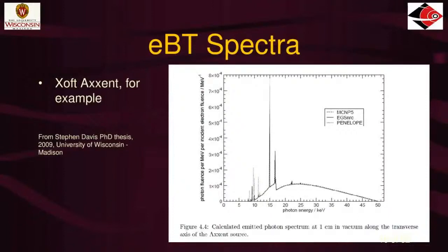Here is the calculated energy spectrum of an electronic brachytherapy source — the Xoft Axxent — shown from three different Monte Carlo codes on the same graph. This is in vacuum, so there's no attenuation in air, water, or tissue. It looks different from a standard X-ray beam spectrum and is lower energy. The filtration is different — it comes out through a water cooling catheter, whereas standard beams are filtered with aluminum, copper, or materials like a Thoraeus filter. X-ray beams are filtered for different purposes: to treat patients, harden the beam, or for diagnostic purposes. The EBT filter serves a completely different purpose.